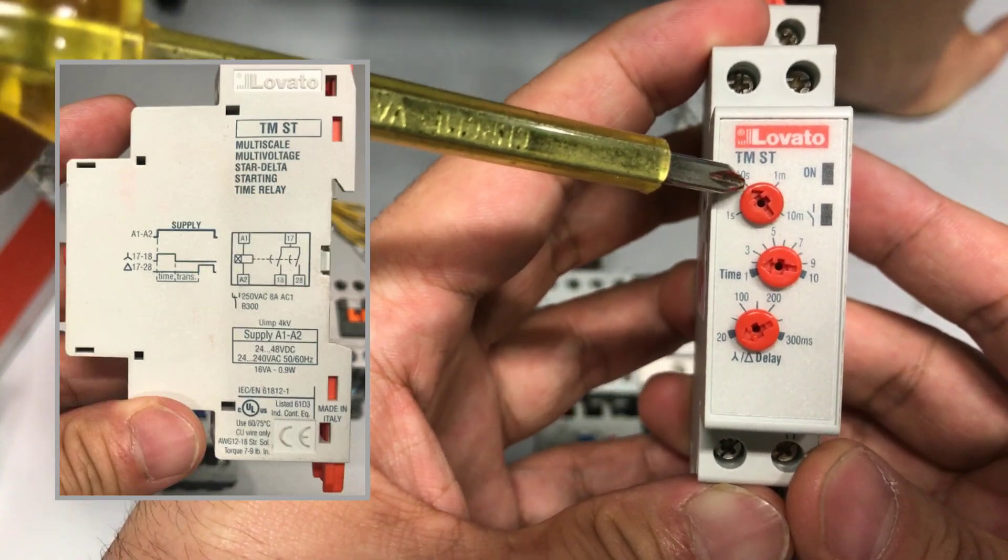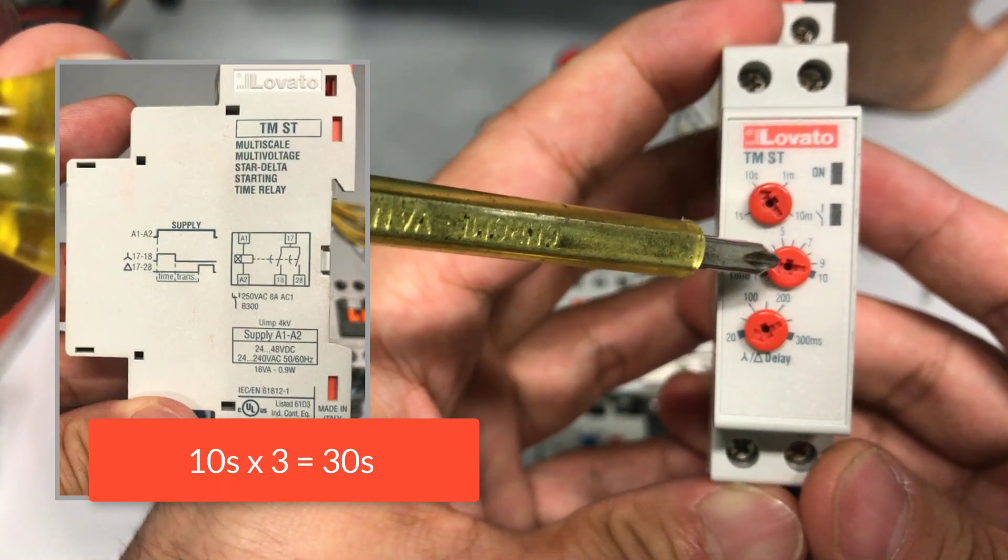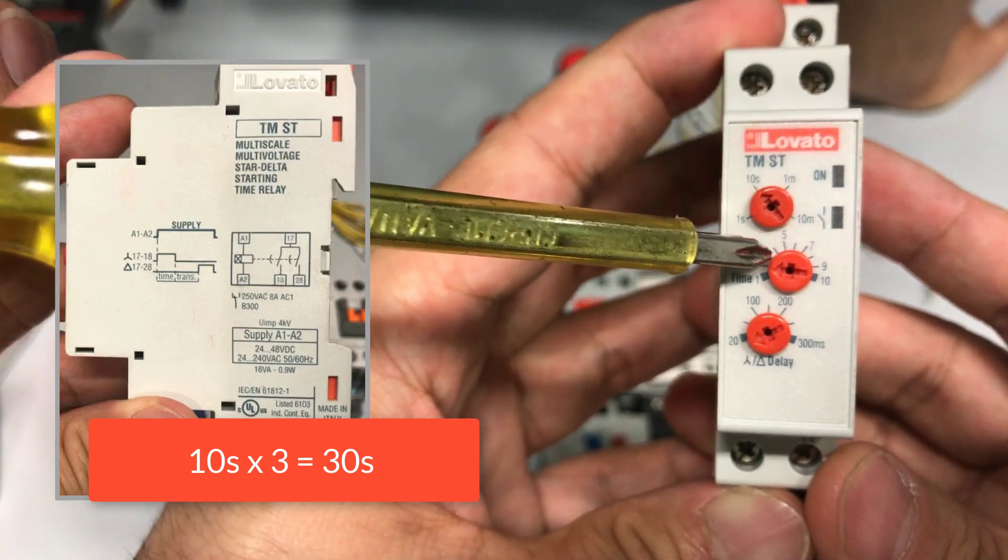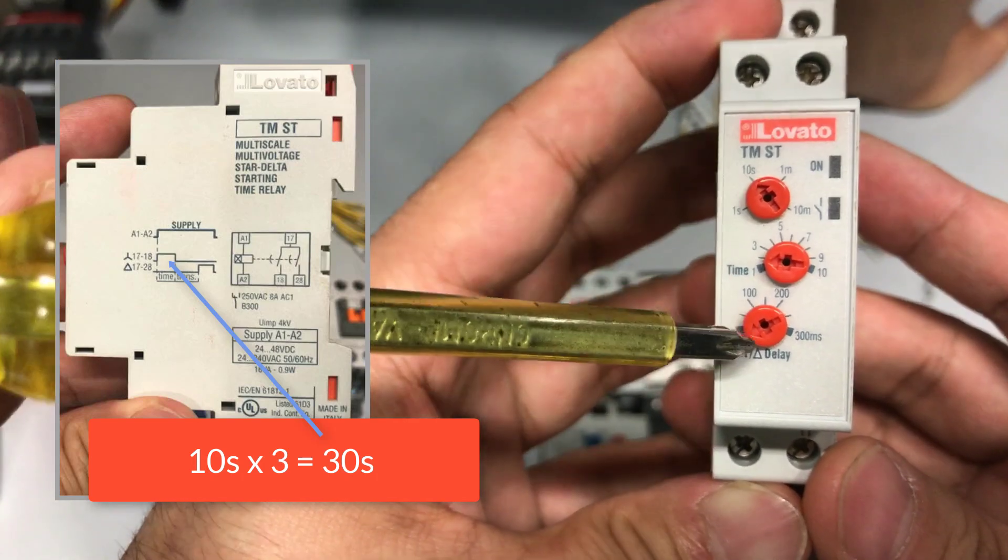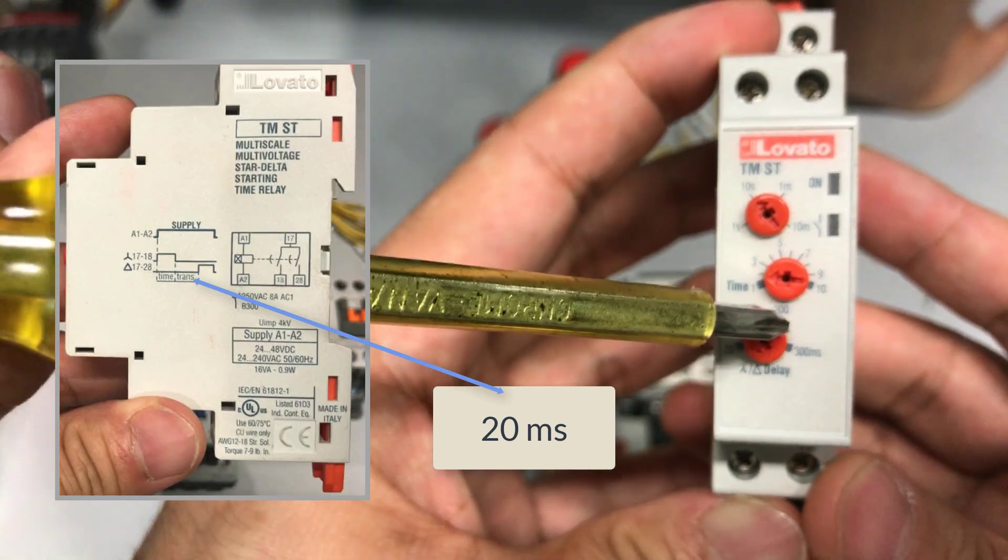The last setting is the period to delay between the star and the delta. For example, if we set this to 10 seconds, set this time to be 3, this will mean that the star contactor will be on for 30 seconds, so 10 multiplied by 3. The delay here has a minimum of 20 milliseconds.